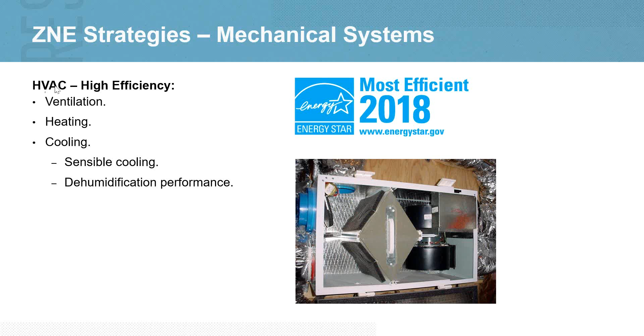Cooling: again, we want high-efficiency cooling systems. I call out two sub-bullets here. Sensible, that's reducing our temperature. But the second part is also really important to consider: dehumidifying. You might imagine our building envelope is really well insulated and air sealed now, so maybe I used to turn on the air conditioning in early April, but now because that shell is so good, my thermostat isn't calling for cooling, but I still have humidity, maybe from outdoors, maybe from indoor sources. We want a good strategy to dehumidify the air so we're not stuck with high humidity levels, which can lead to mold and uncomfortable conditions. The two main strategies: a standalone separate dehumidification system, or a higher-end central cooling system which can operate not only on a temperature setting but also on indoor humidity.